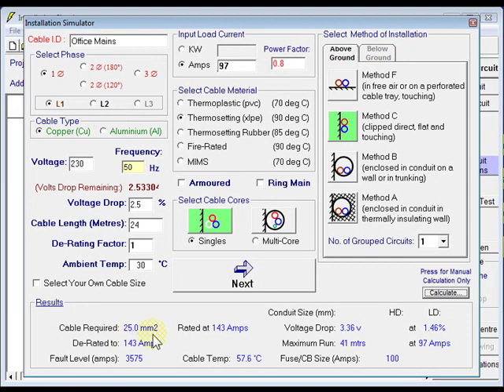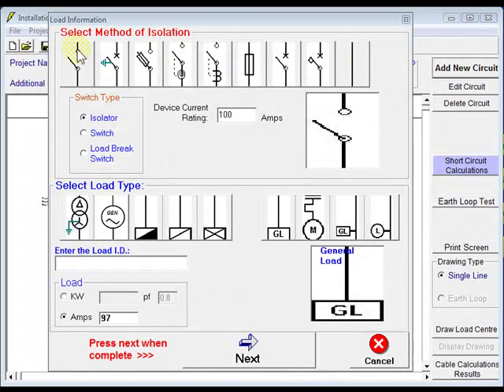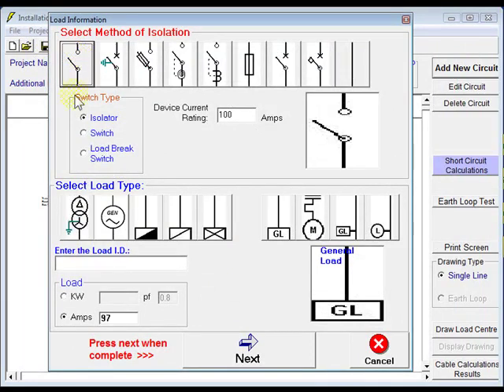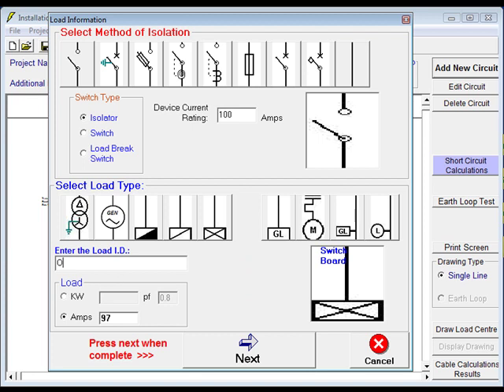It's giving us a 25 mil, we go straight through there, click next. Method of isolation, it's 100 amps load. We're going into a switchboard. We'll call this one office DB, 97 amps of load, click next.